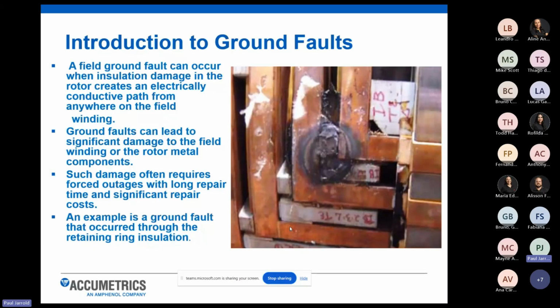And there's always a risk that if you have a ground fault, you can create a shorted path, or a path of least resistance, from the field windings to the rotor itself. In that case, as you can see in the image here on the right, it caused some damage where it actually melted the rotor field windings together and caused a situation where the customer had to stop their generator, investigate, troubleshoot and fix the problem. So it's a significant issue in power generation, and customers are very concerned about rotor ground faults.